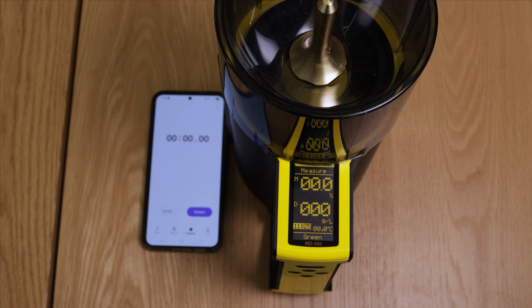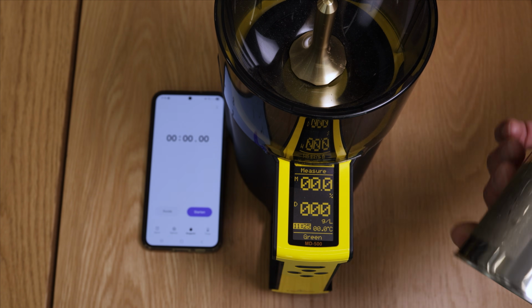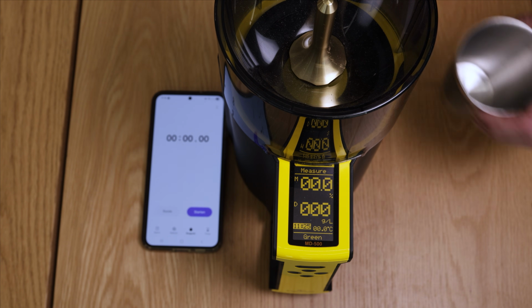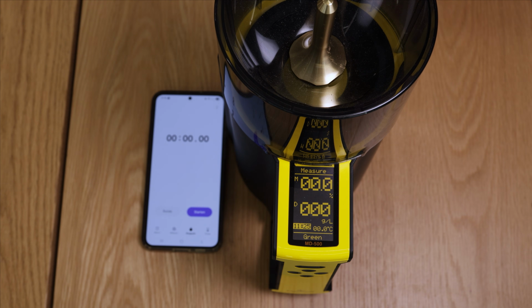So we are going to prepare the sample now. In case of the Lighttells, you will get this cup. It's super important that you don't lose this cup, because if you do, you're going to have an issue, because this is perfectly calibrated so that you get the right amount of beans in the device. So take this one, fill it with beans. Also, you get a little ruler. Take all the beans that are over the rim, put them in the chamber now.